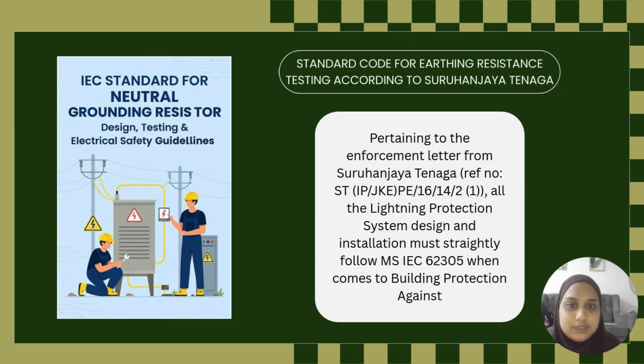Okay, so now I will explain about the standard code for earthing resistance testing according to Suruhanjaya Tenaga. This standard code is used to make sure that earthing resistance testing is carried out according to the requirements set by Suruhanjaya Tenaga. Based on the enforcement letter issued by Suruhanjaya Tenaga, all lightning protection systems, which is LPS, must follow the code MS IEC 62305. In simple terms, MS IEC 62305 is a guideline that explains how to properly protect buildings from lightning.